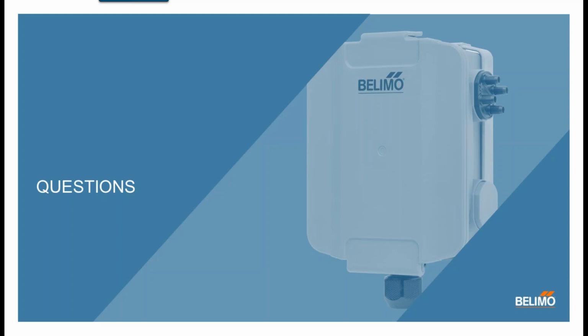The temperature sensor type for CO2, if I think I understand it correctly, is a 0 to 10 out, and so you'd have two 0 to 5 or 0 to 10 outputs for both temperature and CO2, if that's how I understood it. Okay, we have a two-part question. Are all of these sensors available through current distributors? And are they delivered to the market through the same channels as valves and actuators?